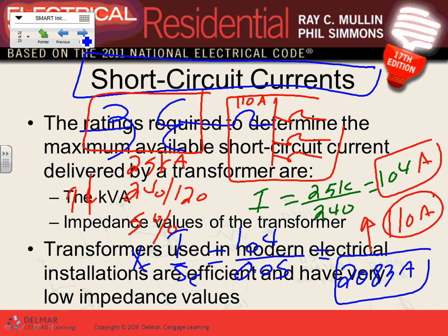Now, if I put 2K here, 2 kiloamp, am I covered for this short circuit? Yes. Done. That's what typically you have in an apartment building or a dwelling building. You're going to have a 10K circuit breaker, 100 or 110, fed from a transformer, 15, 20, 25, like this.